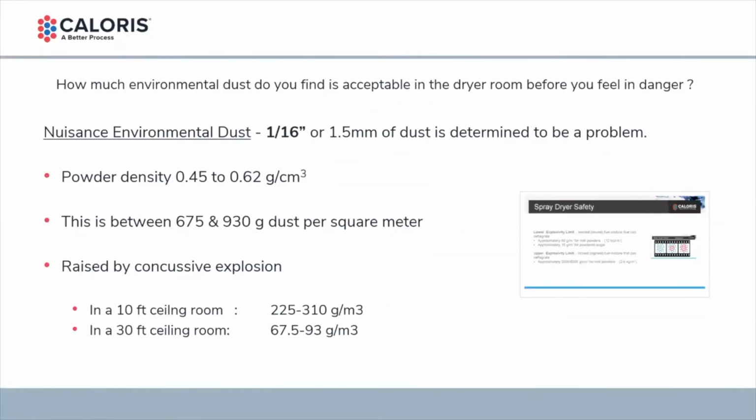So here's that question again. Of the 60, this is where I'm asking you to remember the 60. How much environmental dust do you find acceptable when you walk into a dryer room? You're attending this webinar probably because you have some responsibilities for a spray dryer. If you walked into the room and saw dust on the ground, at what level, what depth? Does it have to be 1 inch deep before you get worried about it? Does it have to be 2 inches deep? Well, the answer is right there. The answer is 1/16 of an inch of dust.